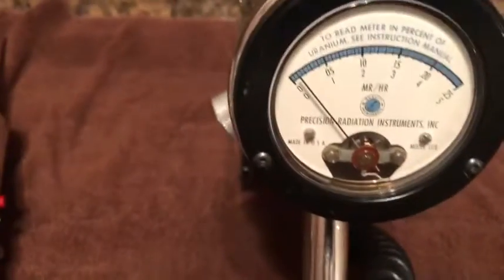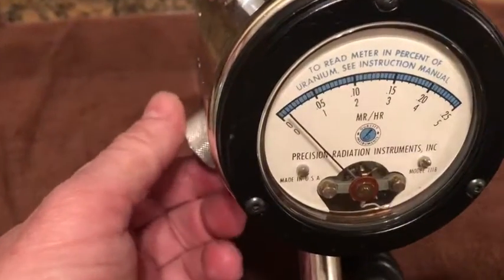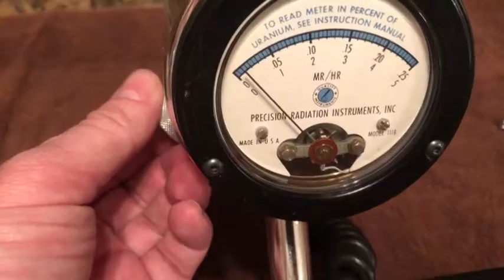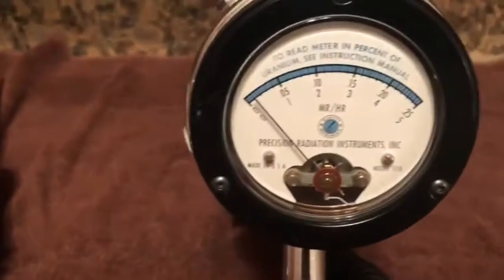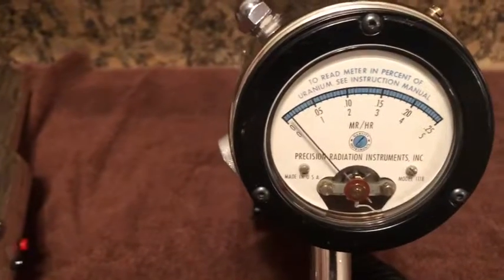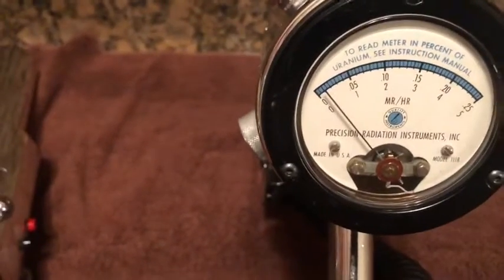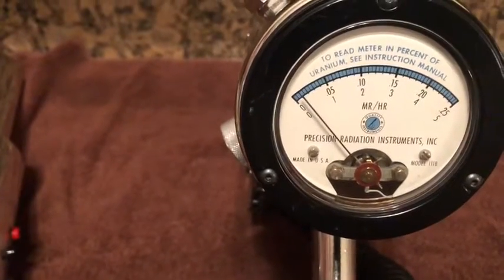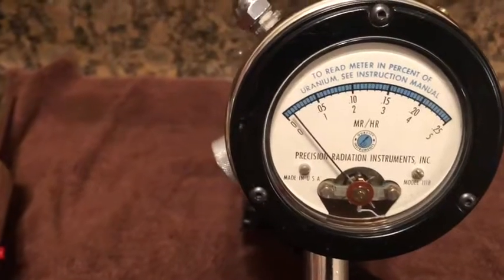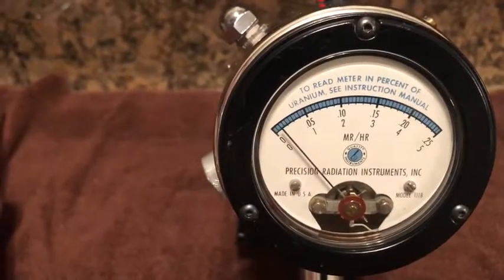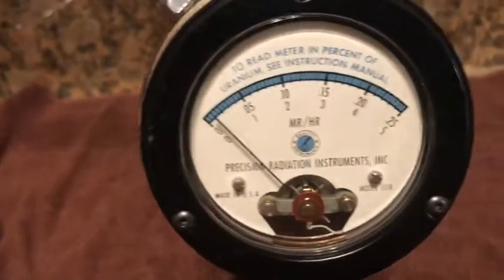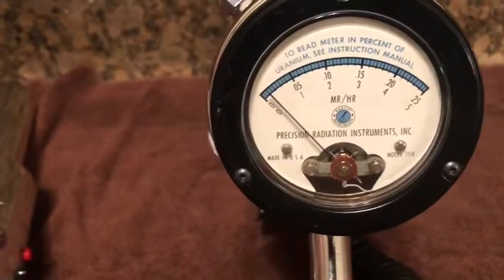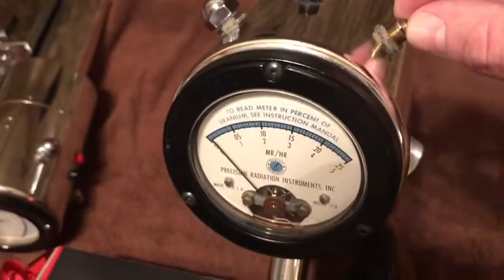What I would normally do for calibration is put the range selector to 0.025. And for me here in the house, the ADM reads a steady 15 microrentgens, which in this case would be 0.015 millirentgens. So if you're not in that zone, if you're reading high or low of the ADM 300, you just go up to this calibration setting and adjust it so it reads accordingly with the ADM 300.